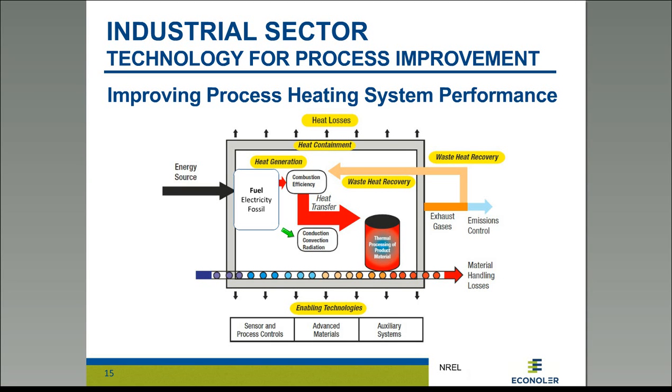So we did work closely with the manufacturer. There was some issue about fire protection and other points that had to be considered, but we did change the design and how the conduction, convection, and radiation were used to transfer heat to the meat, and we were able in the end to reduce by about 15% the energy consumption of this particular plant. So there are definitely things that can be done on those kinds of equipment.